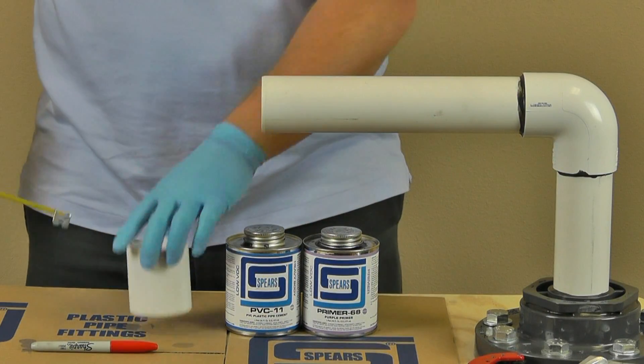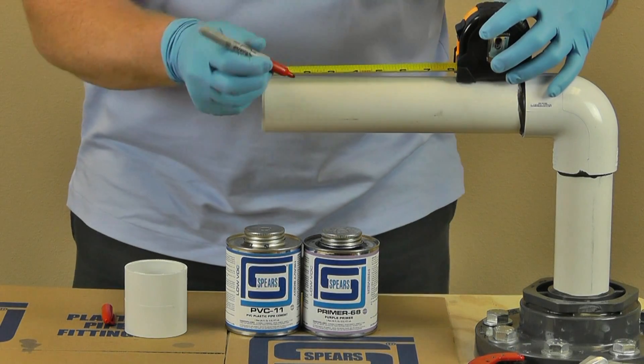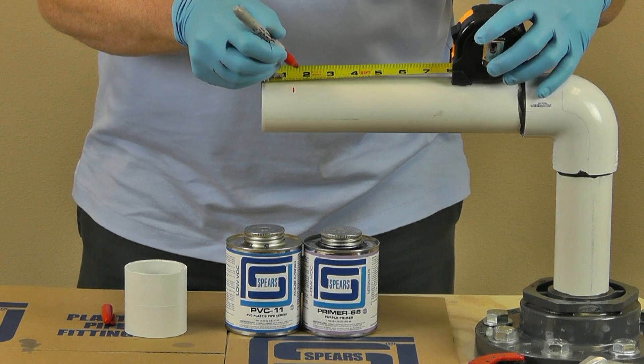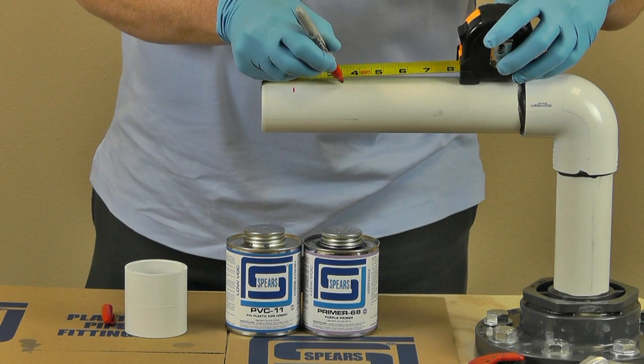Fourth, measure the inside length of the fitting socket. Mark this length on the outside of the pipe and make another mark 2 inches above the first mark. This will indicate how far up the pipe the primer and cement are to be applied and provide visual verification that the pipe has been fully inserted into the socket.